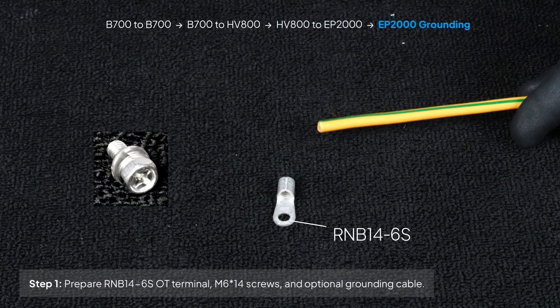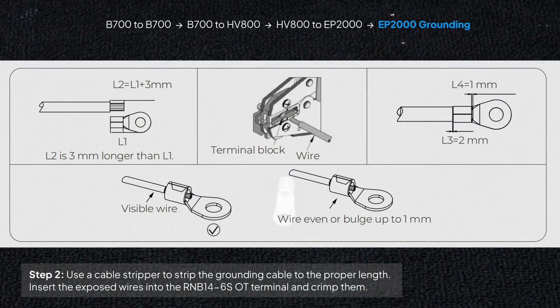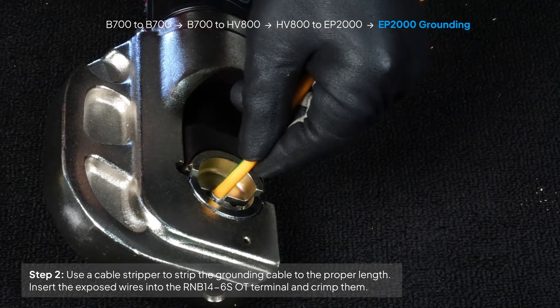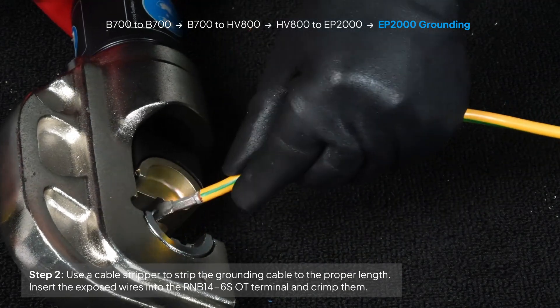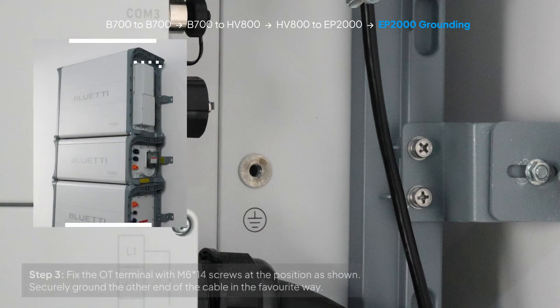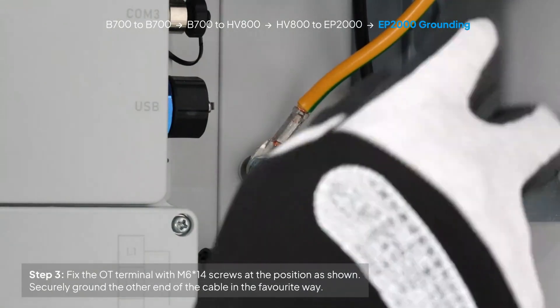Prepare the standard RNB14-6S OT terminal, M6 by 14 screws, and an optional grounding cable. We recommend using a 10-square-millimeter yellow-green outdoor cable. Then use the stripper to strip the insulation layer to a proper length. Insert the exposed wires into the OT terminal and crimp them together. Attach the OT terminal to the designated position as shown, then securely ground the other end of the cable using your preferred method.